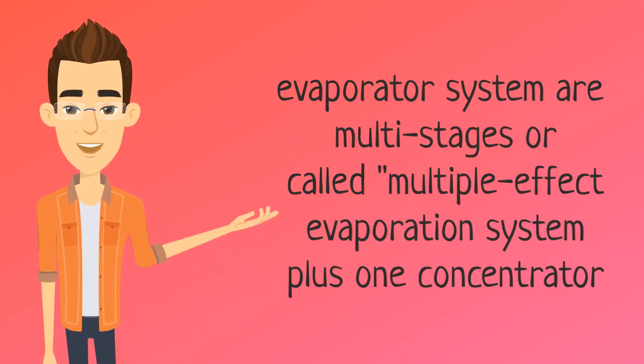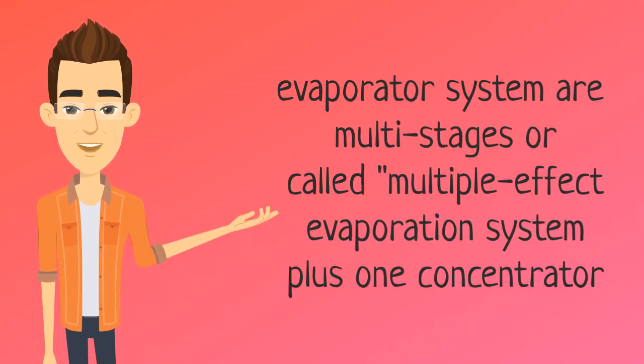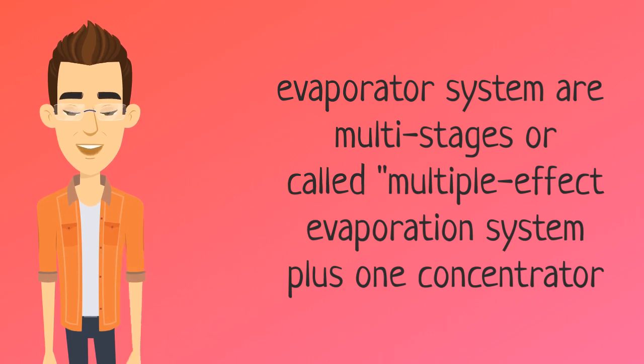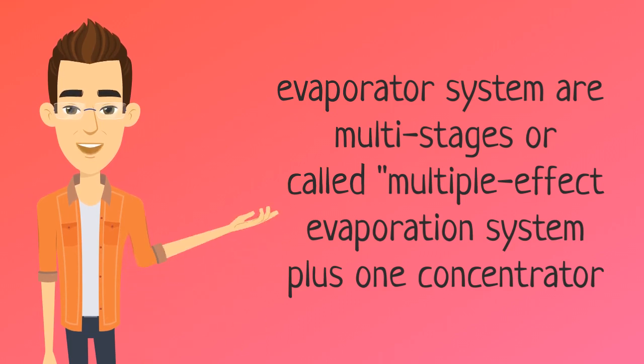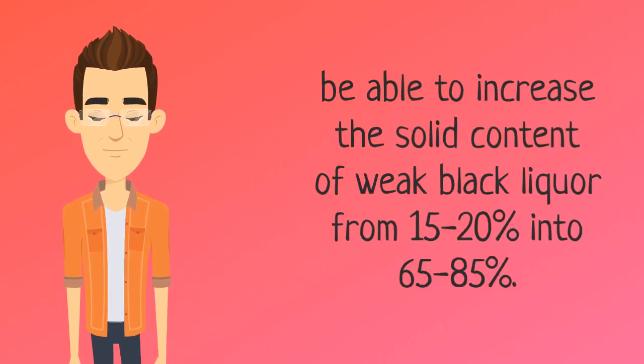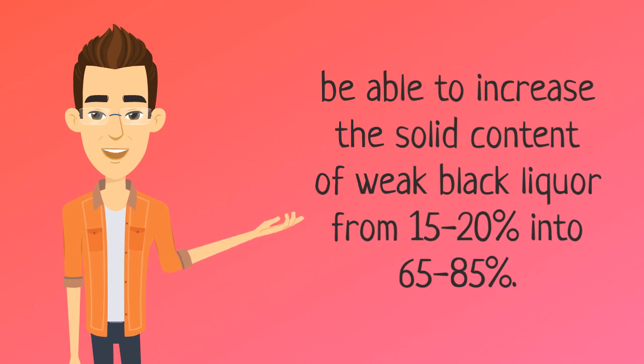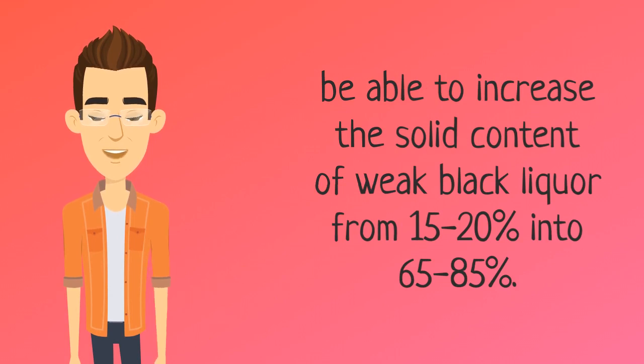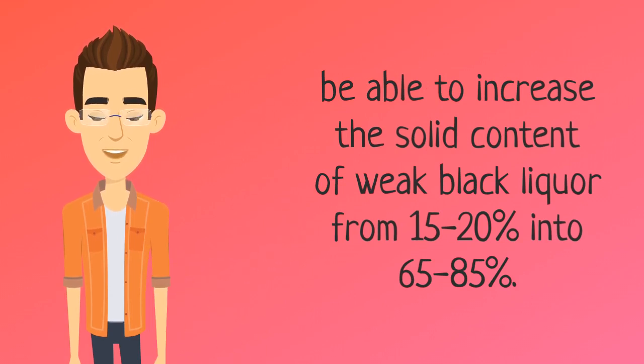The evaporator system is a multi-stage system, also called a multiple effect evaporation system, plus one concentrator. It increases the solid content of weak black liquor from 15 to 20 percent up to 65 to 85 percent.